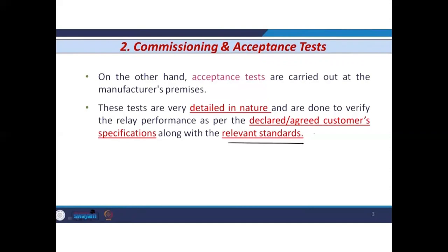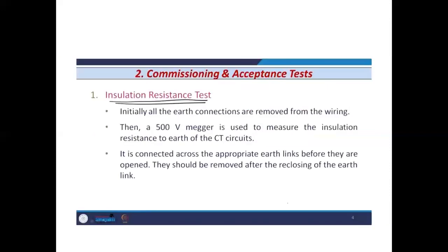So whether he will accept these protective devices depends on this, because if these devices are not according to the relevant standards or the specification as ordered, the customer will never agree on these protective devices. So these tests are carried out to check whether the customer agrees with the specification provided by the manufacturers. The first one in the commissioning and acceptance tests is the insulation resistance test.